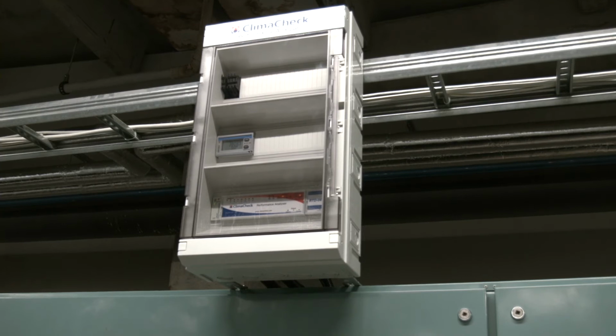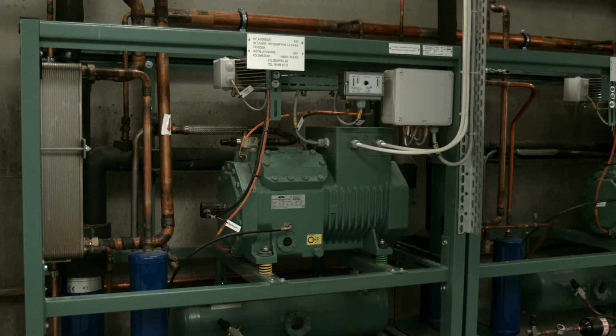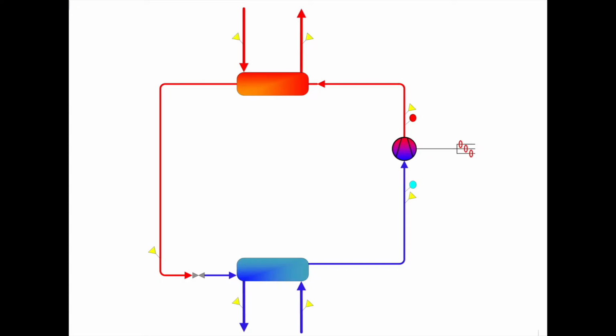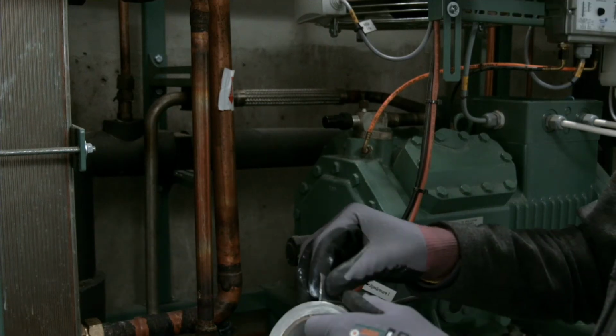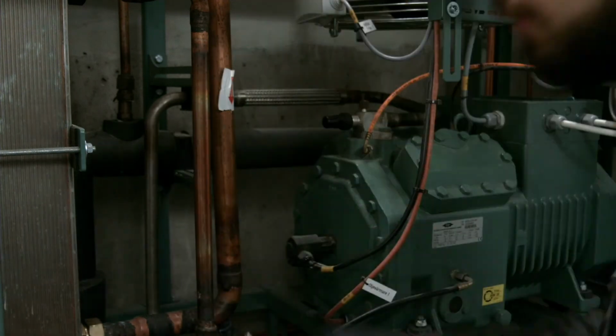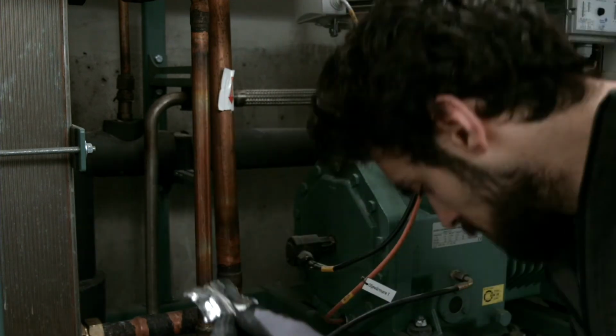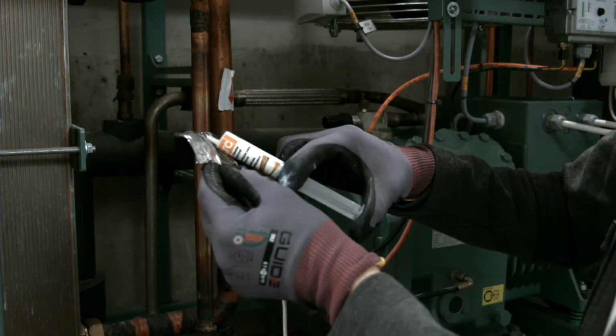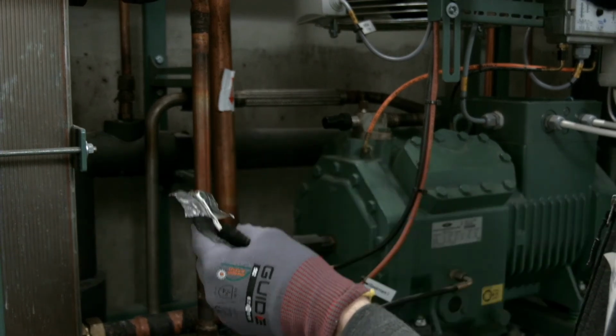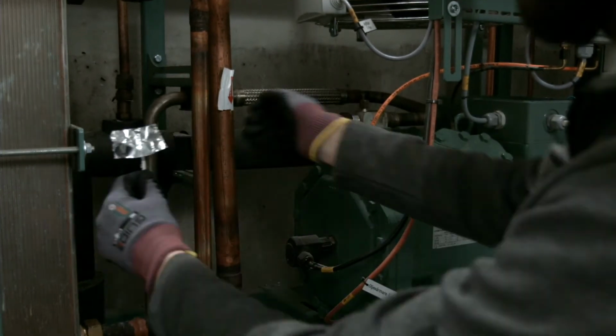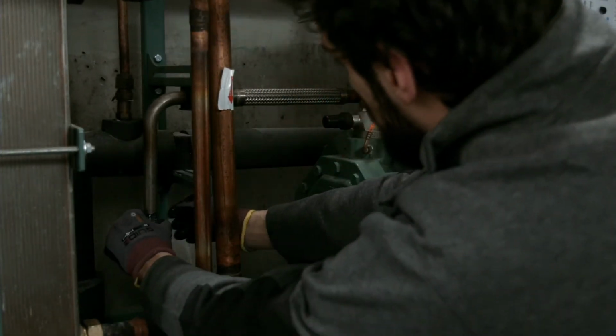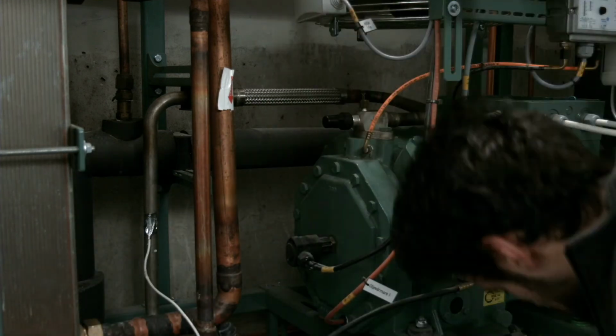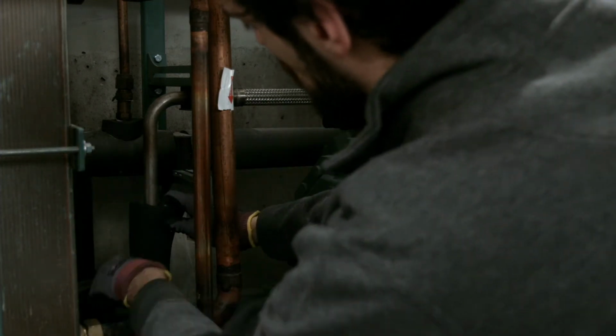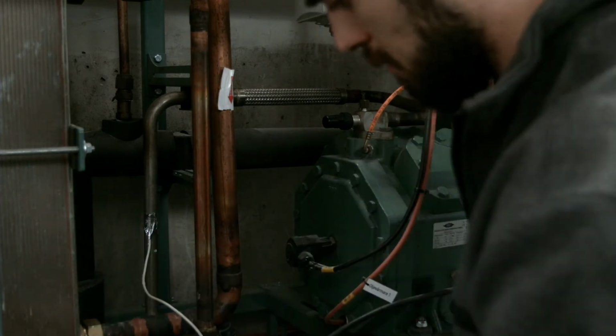In this video you'll see the sensors being connected to a system. We've sped the video up. So a simple system in this particular case. First we have to connect temperature sensors. These are PT1000 sensors. You apply a heat paste and silver foil and simply fix this to the appropriate refrigerant line, discharge, suction, liquid line, etc. Once attached with the silver foil, insulation is then applied to ensure a good contact and no heat loss around the sensor.